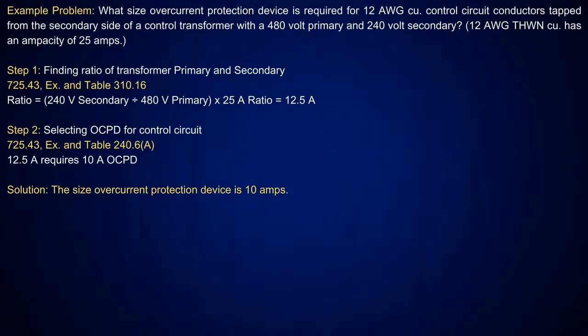Okay. No worries. All right. Then we're going to do another one here, and this is where we're going to size the overcurrent protection device. What size is required, where I have number 12 control circuit conductors that are tapped from the secondary side of a control transformer. And the primary is 480 volt and the secondary is 240 volt.